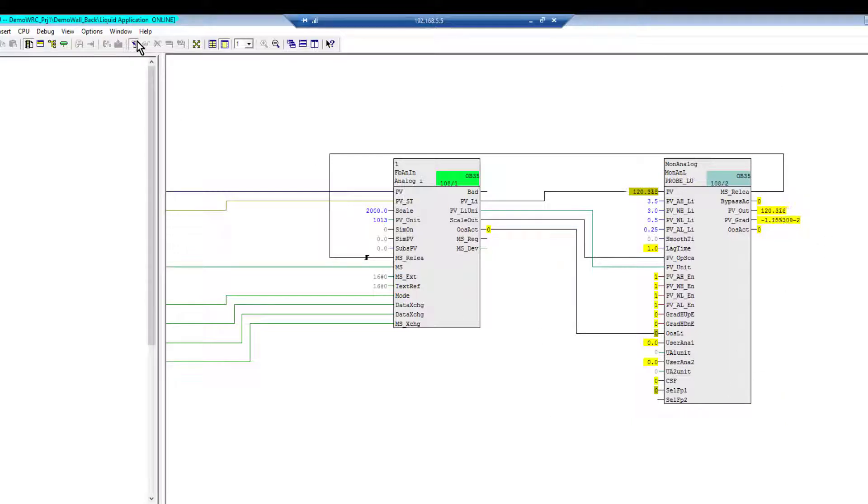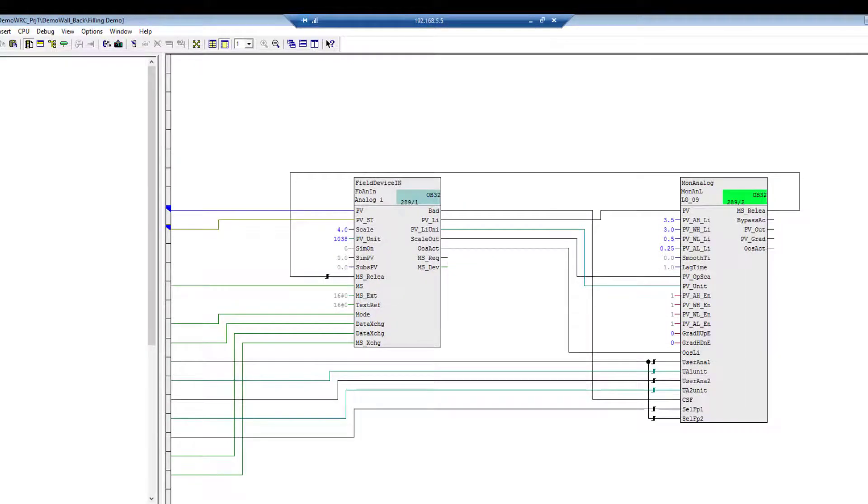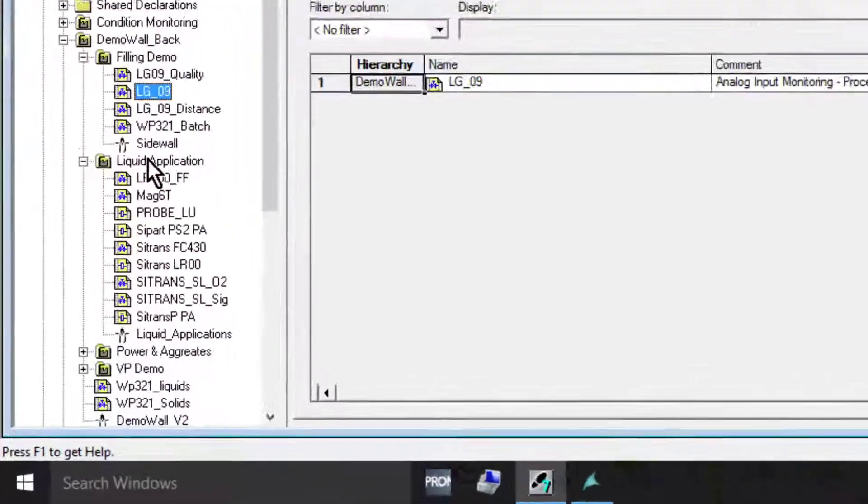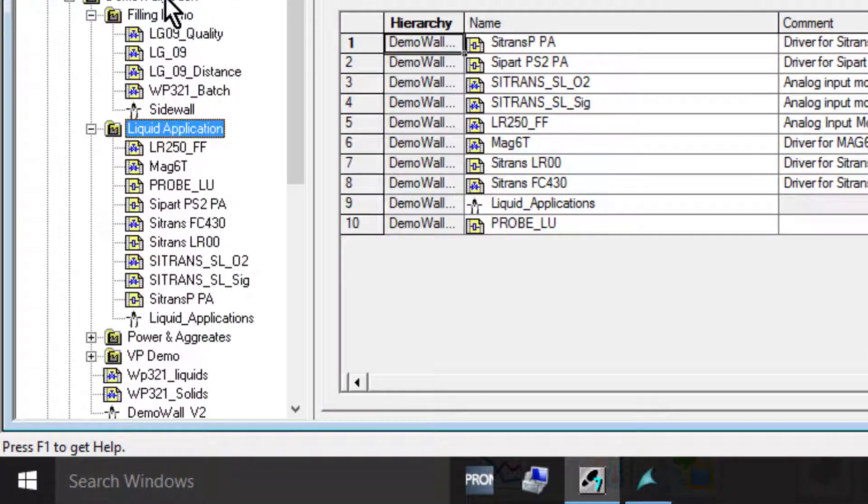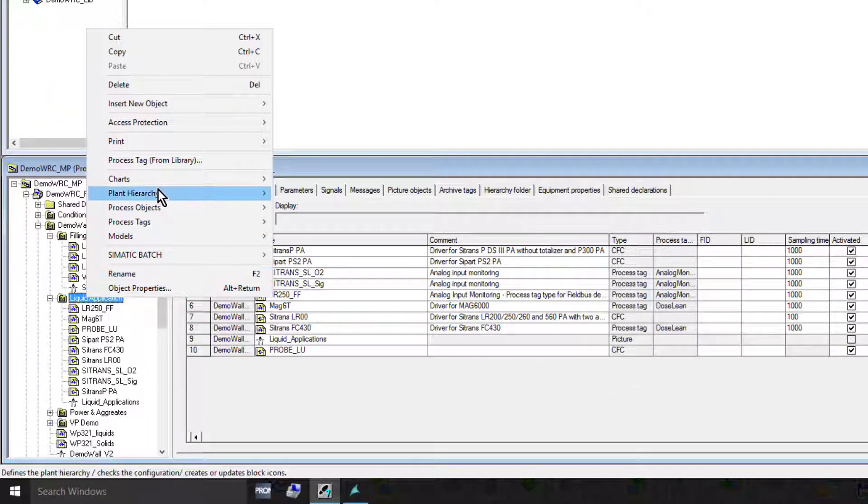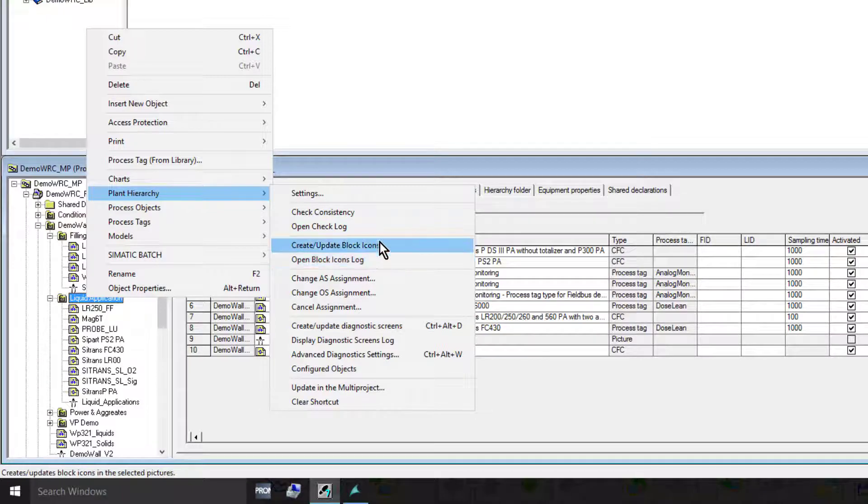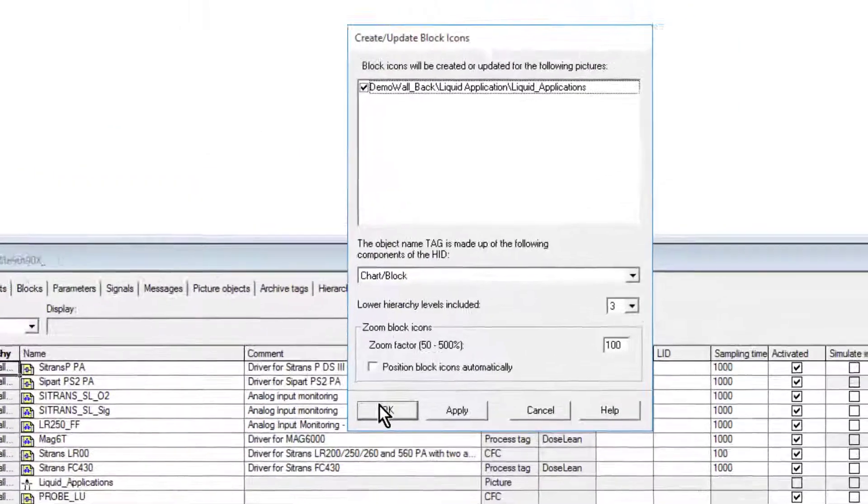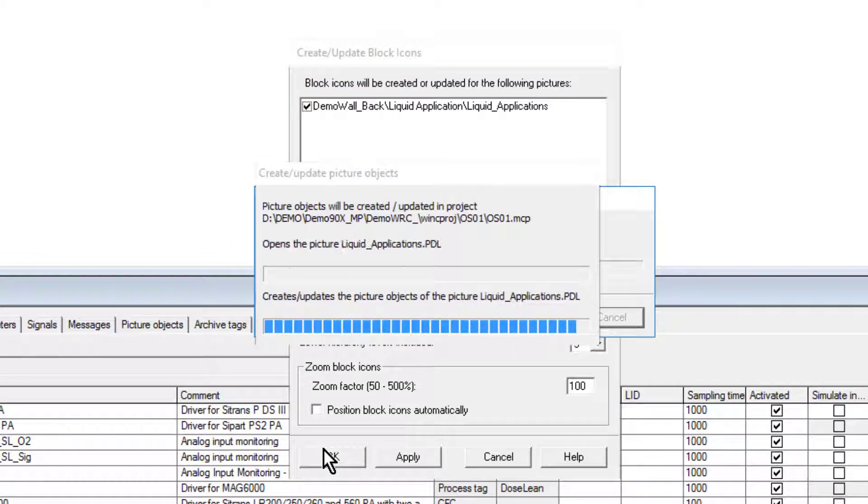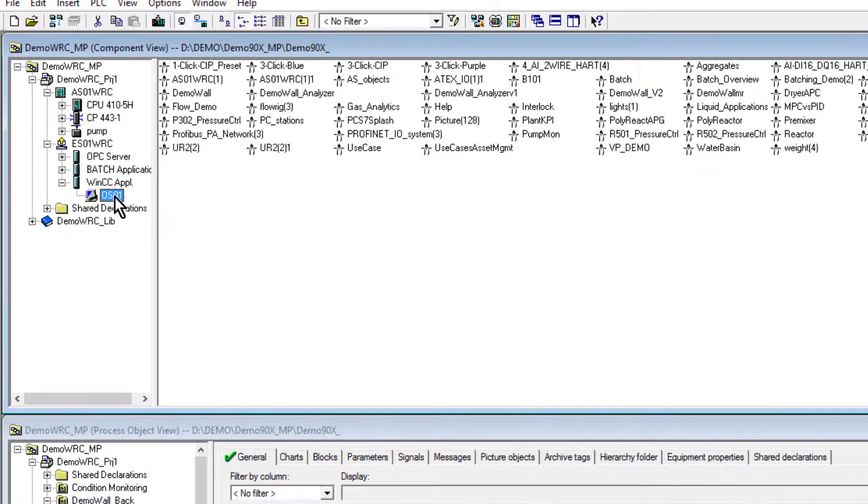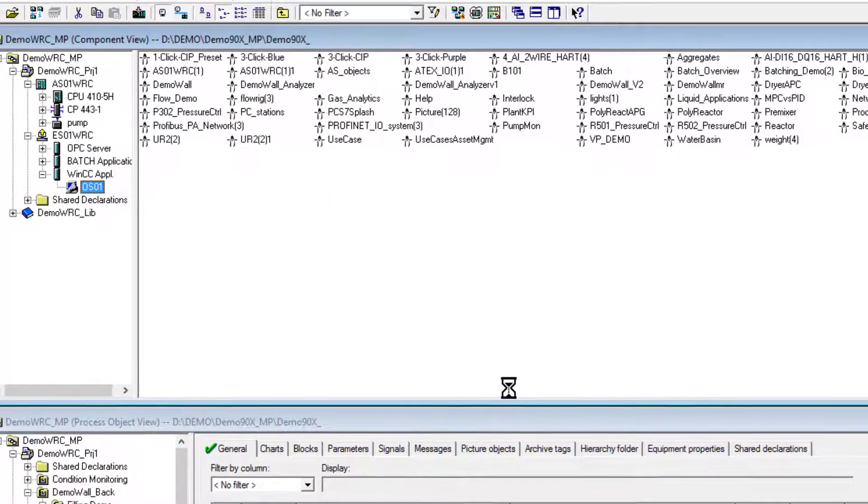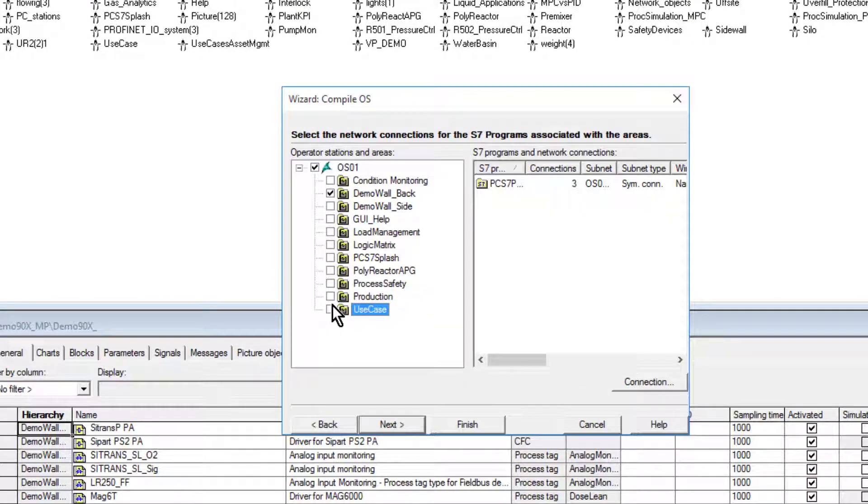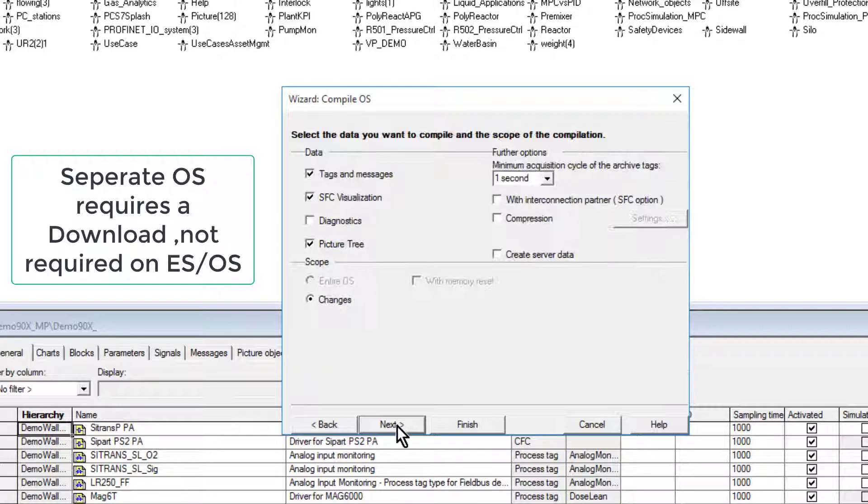That takes us to visualization. If I close this down and go to my liquid application where my ProVal is, I'll right click Plant Hierarchy and Create Block Icons. The last thing I need to do after creating my block icon is compile my OS. Don't forget, as I mentioned in previous blogs, this demo room is an ES and OS, so all I'd have to do here is a compile and then refresh my screens. But if it's an OS I would have to do a compile and then a download.